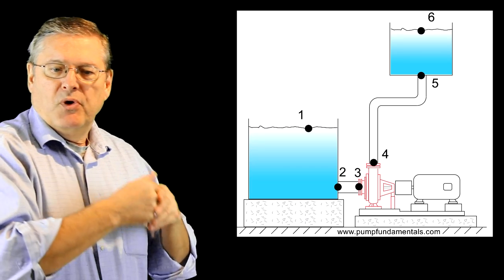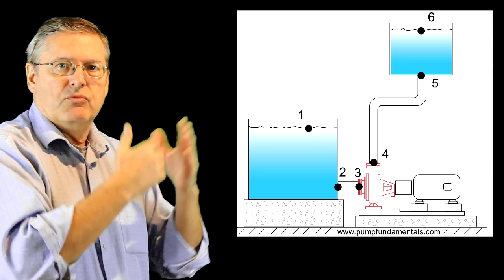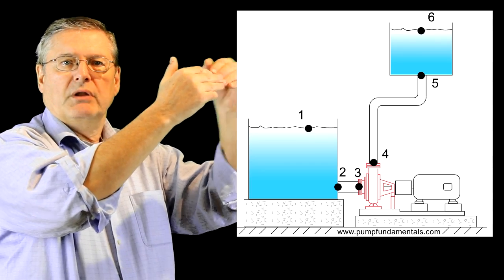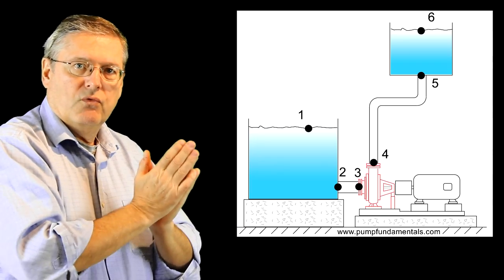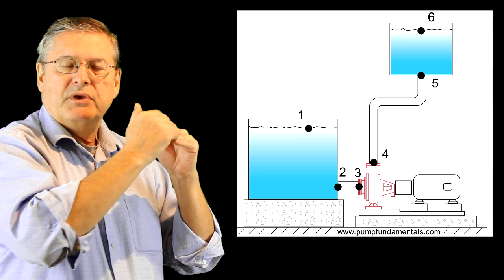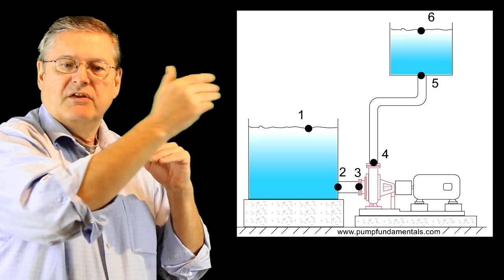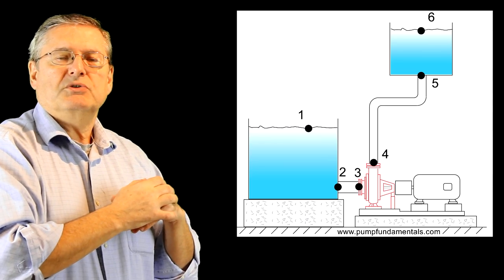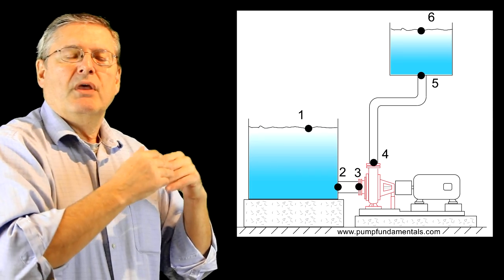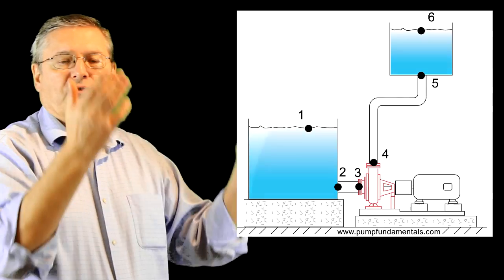Point three has the same pressure as two minus a little friction loss in the pipe. Point four is the pressure developed by the pump. Point five is right under the upper tank — as we go up we lose pressure because there's less weight of water, so pressure at five equals pressure at four minus the pressure corresponding to that height minus any friction loss. Finally, point six is at atmosphere again, so there's zero pressure.